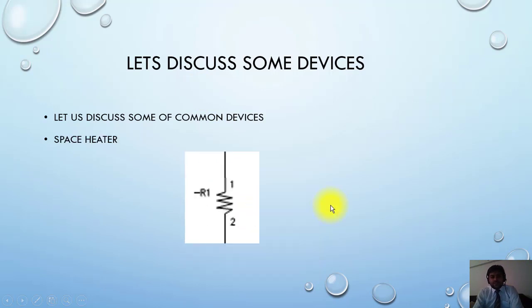Next item, this shape is in the shape of a resistor, but in our drawing it's shown as a space heater. Each control panel also has a space heater. The function of the space heater is to reduce the moisture. Moisture needs to be reduced because if moisture is present, it will cause rust in the panel.